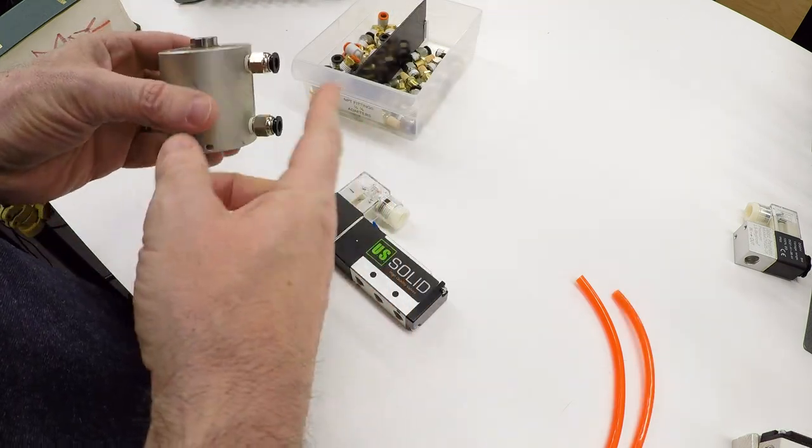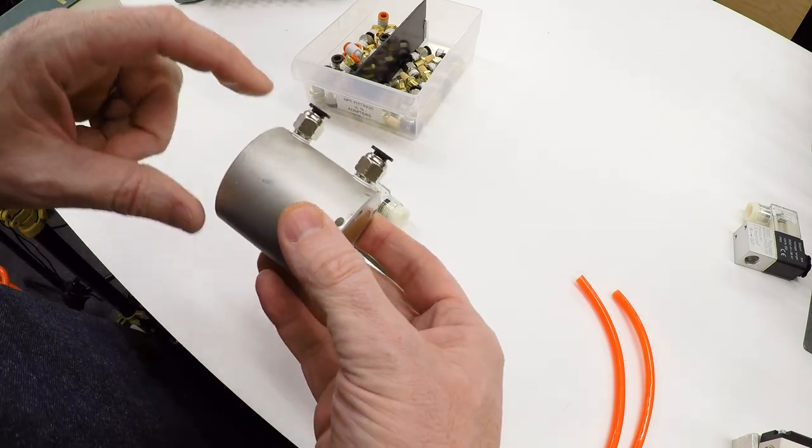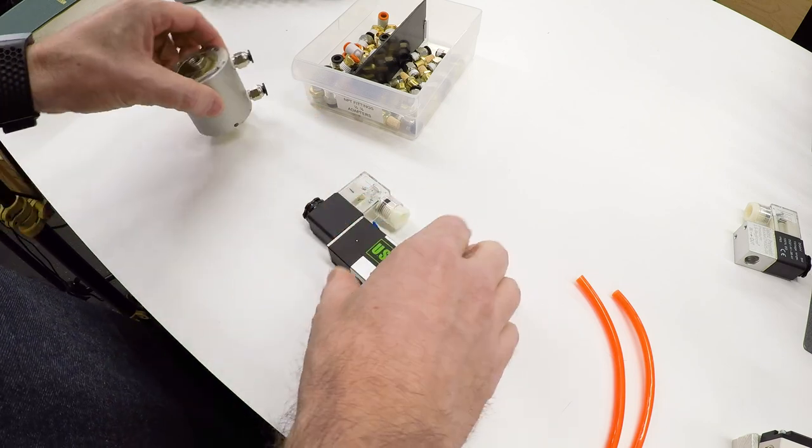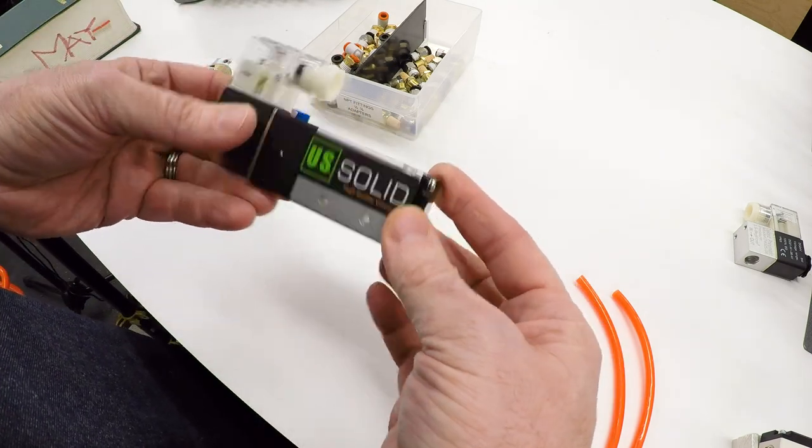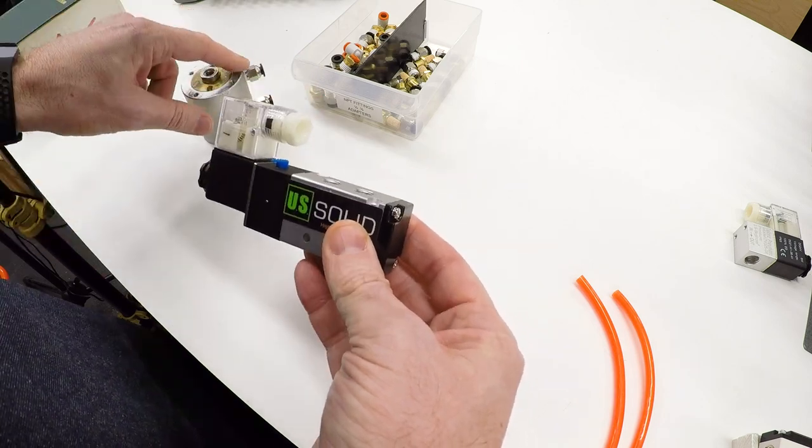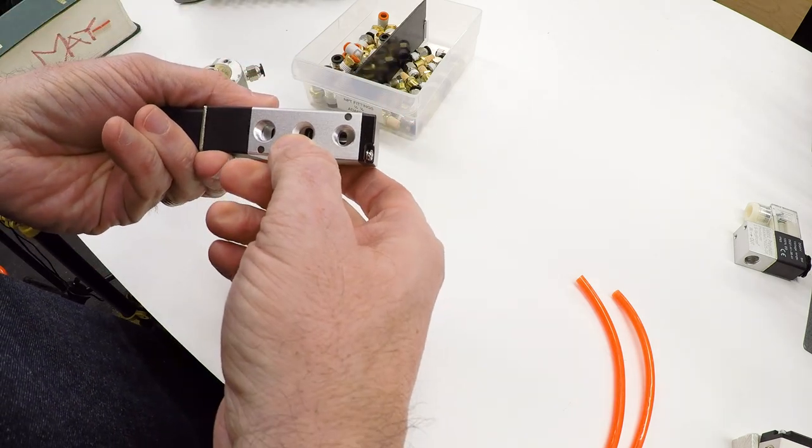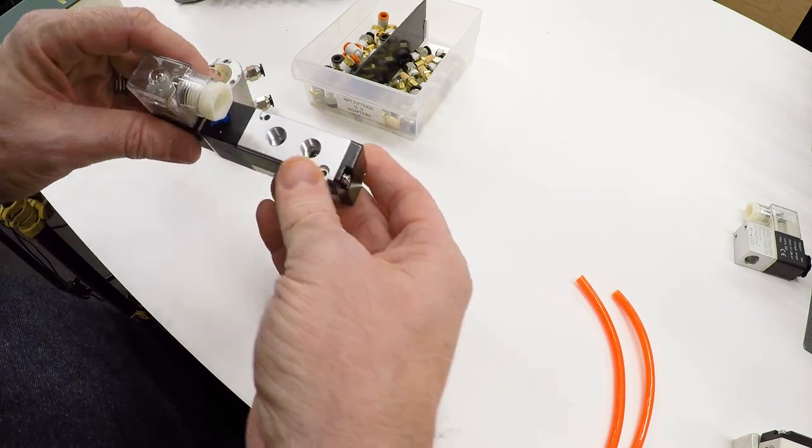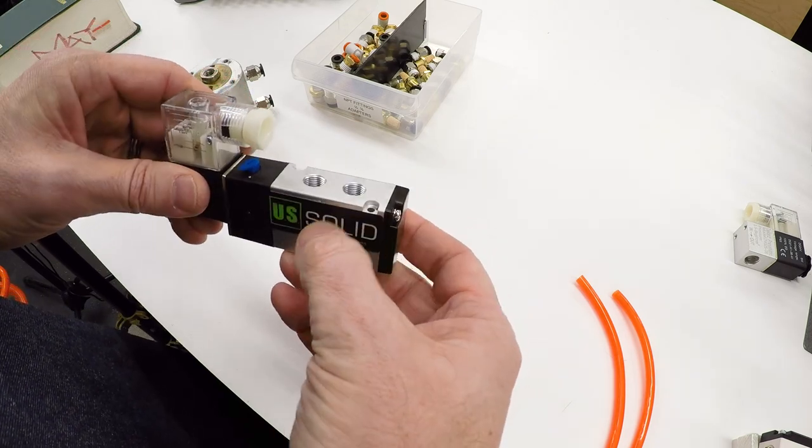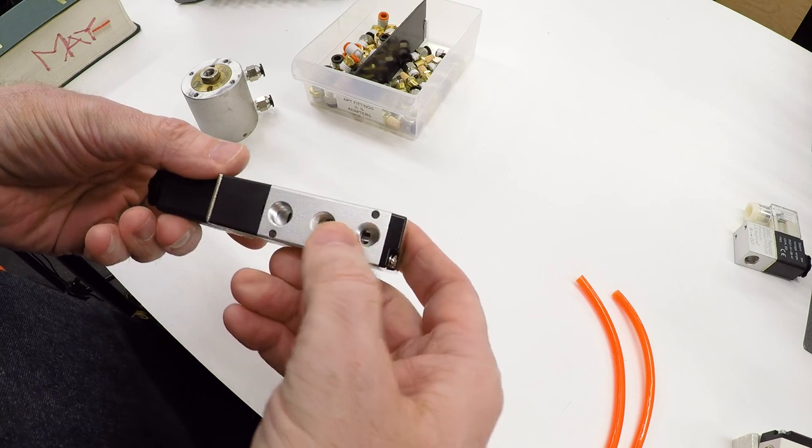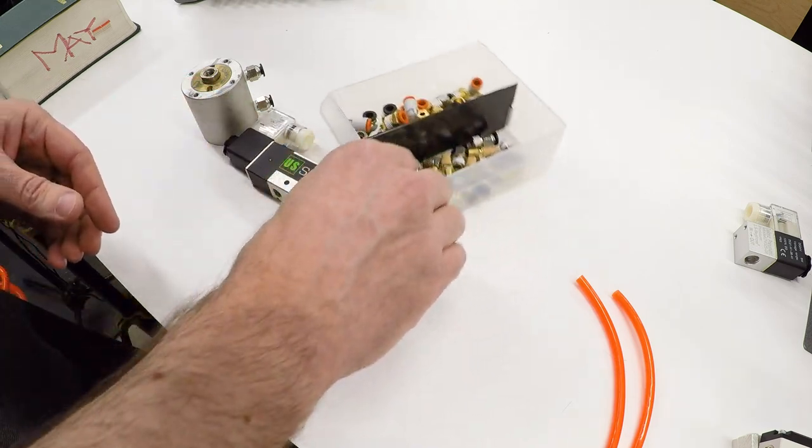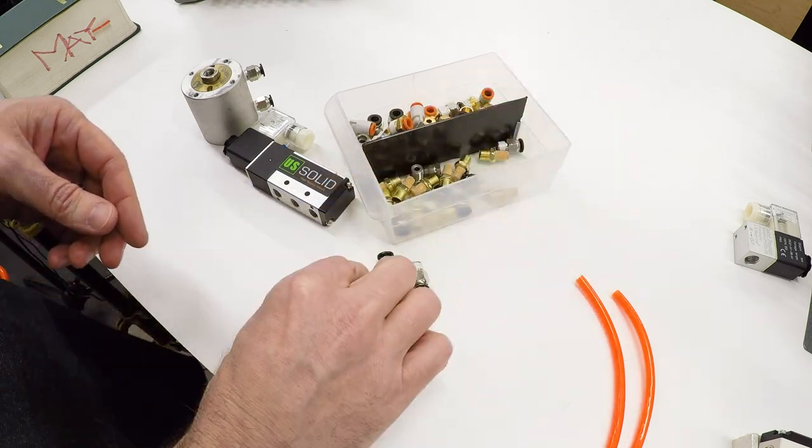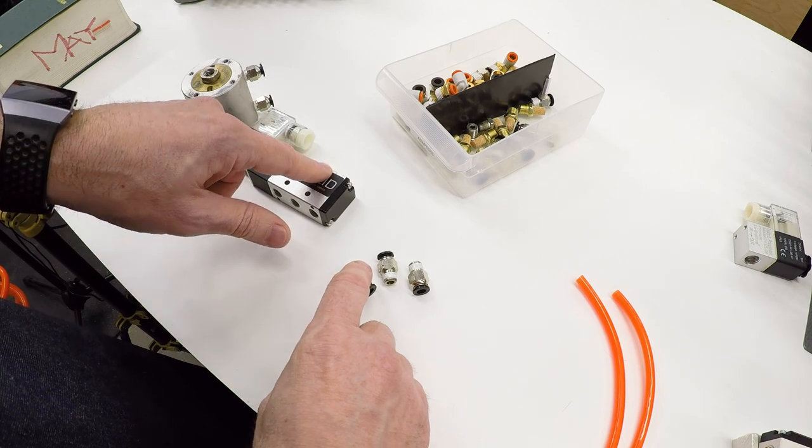I've got a double acting cylinder here and I have already put quarter inch push to connect fittings on the cylinder. So those are ready to go and we're going to use it with a 5-2 valve. These two ports on the top need to be connected to the cylinder. I need to connect pressure to the bottom and the other two are exhaust ports for the cylinder. This particular valve has eighth inch NPT fittings in it. So I'm going to use eighth inch NPT fittings to make the connections.